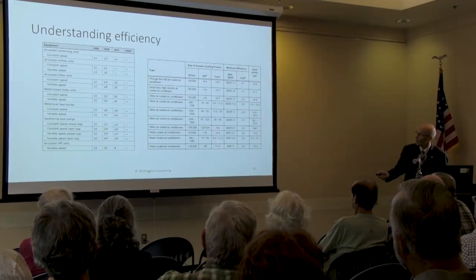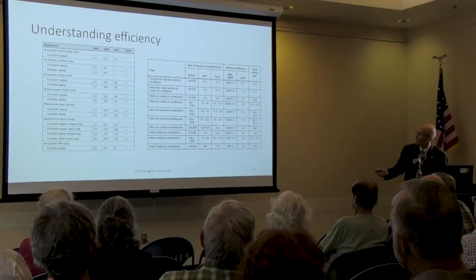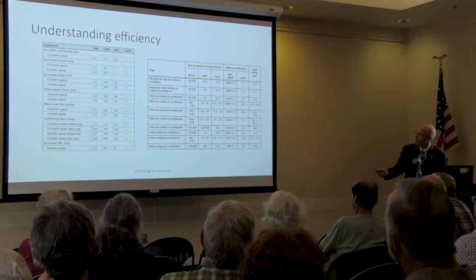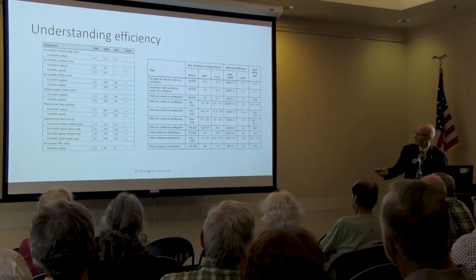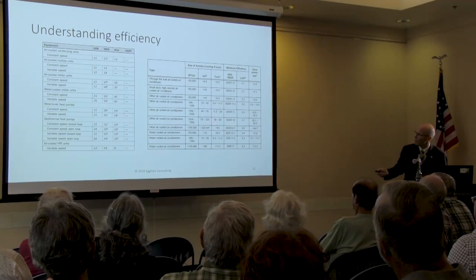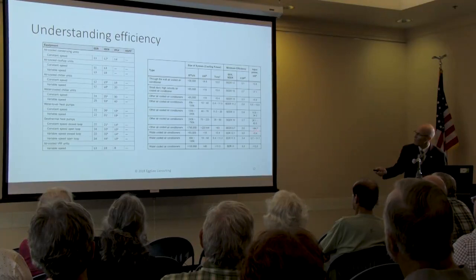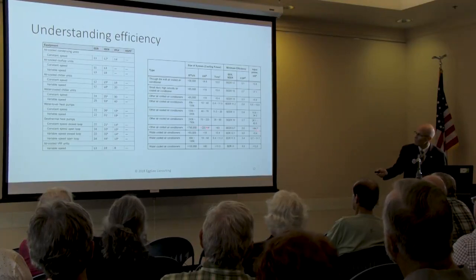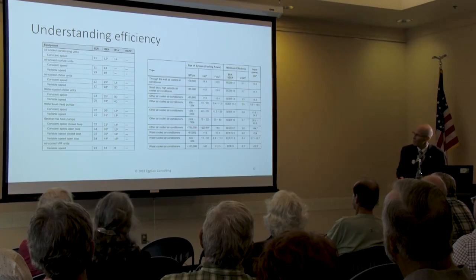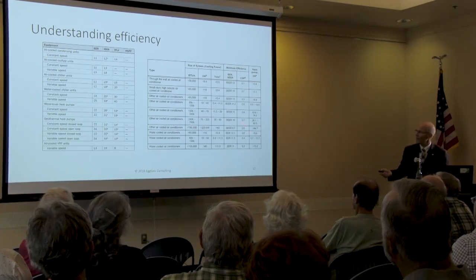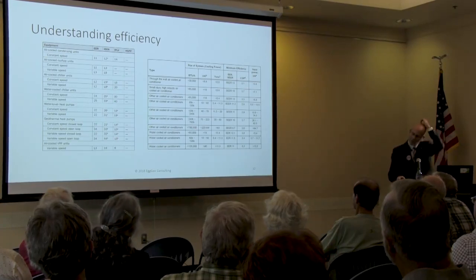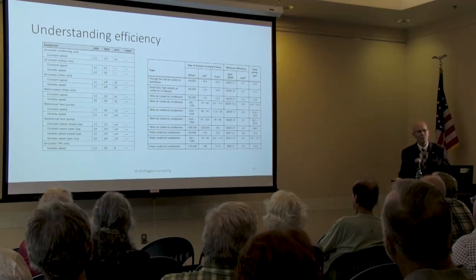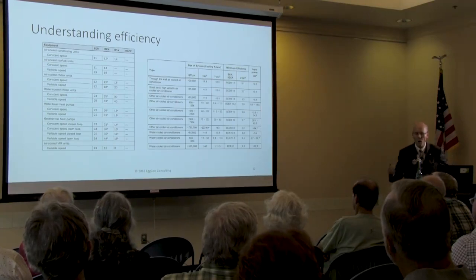So it doesn't matter. You go down here to this 11.3 or this 20-ton unit here. It doesn't matter. I don't know why it's got a couple of different things here. Let's look at this 63-ton unit. It uses 84.7 kilowatts to deliver 223 kilowatts, or 760,000 BTUs of energy at a COP of 2.6. This is not necessarily geothermal, but it just shows a little bit about what's going on in these charts.